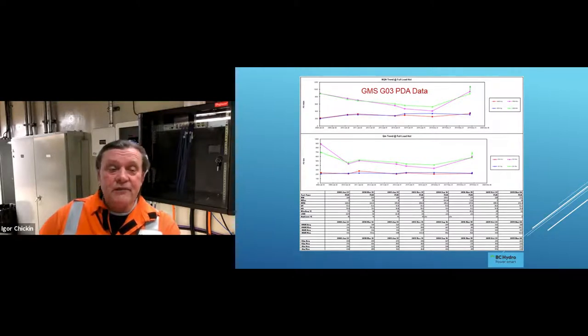And you may look at the very beginning, the PD levels were high, and then we stabilized, but keeping high, like around 600, long-term high. And as soon as that climbs up, we raise the flag and start investigation.